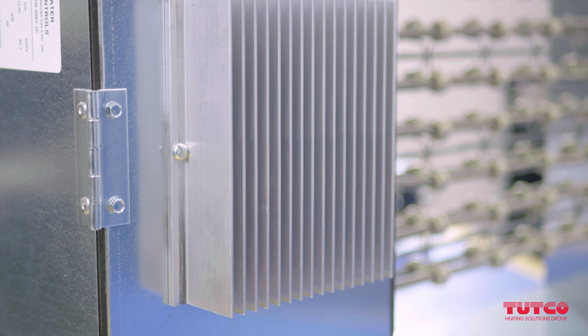I see a step controller here too. How would I know when I need a step controller when I'm getting an SCR? I like to say that if you pick the SCR as an option, the step controller will only come along if it's needed, because anything over that 48 amp mark, step controller will automatically get added to be able to carry the subsequent circuits after the first one. Good. Yep. Excellent. Now I see a few contactors here. I also see some, what are these, thermal limits? They are thermal limits, okay. Yep.